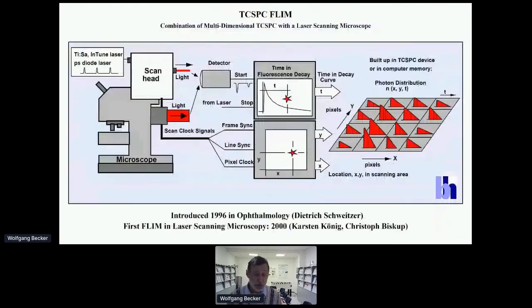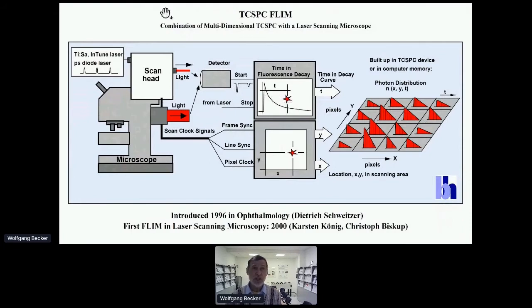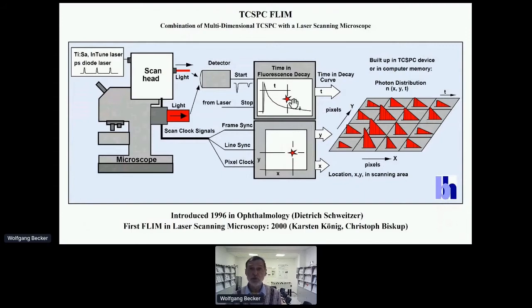How are we recording FLIM? We have a laser scanning microscope using pulsed excitation at high repetition rate. The laser scanning microscope scans the sample with this pulsed laser beam. The fluorescence light goes to a detector that delivers an electrical pulse for every detected photon. We determine the time of this photon in the laser pulse sequence — that is, the time in the fluorescence decay function — and the position of the laser beam at the moment of photon detection. We use this to build up a photon distribution of X, Y, and T, and this is our FLIM result.